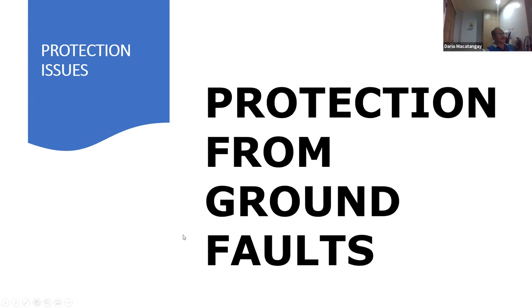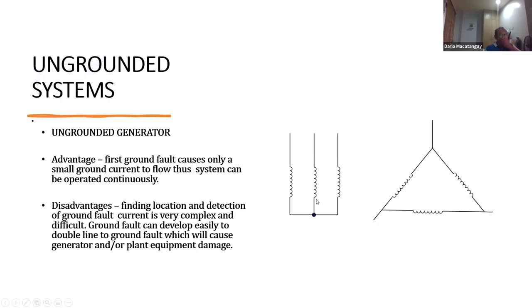Protection from ground faults. All right. So there are types of generator connections that we use. The first type is the ungrounded generator. It could be an ungrounded Y, or it could be a delta connected generator. Now, the problem with this is that, well, firstly, let's talk about the advantage, okay?